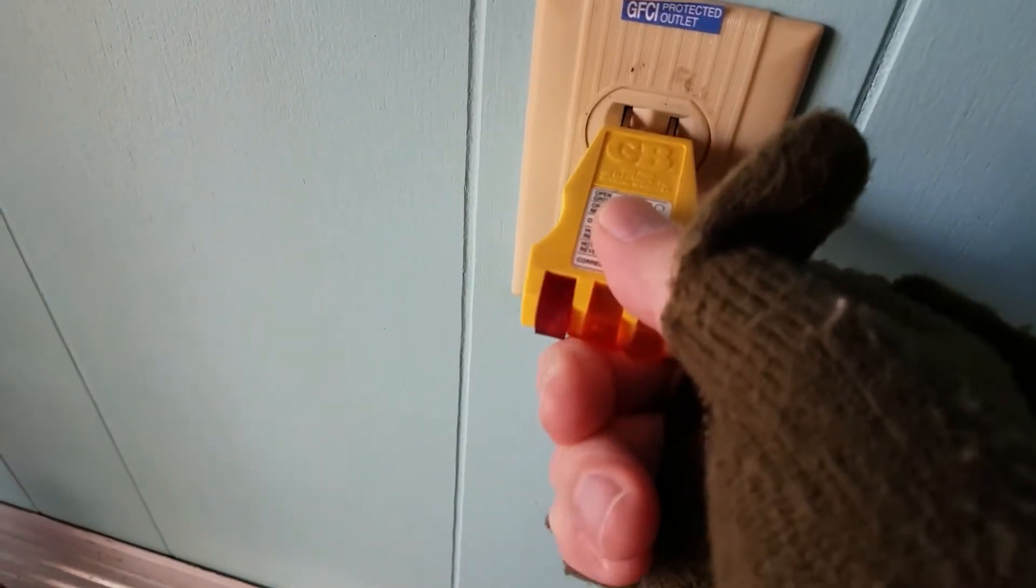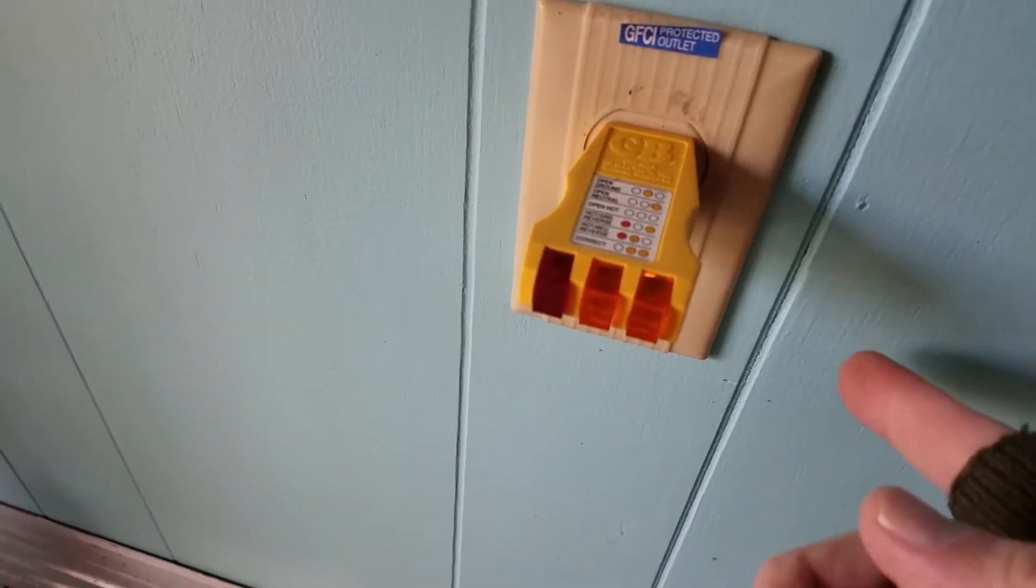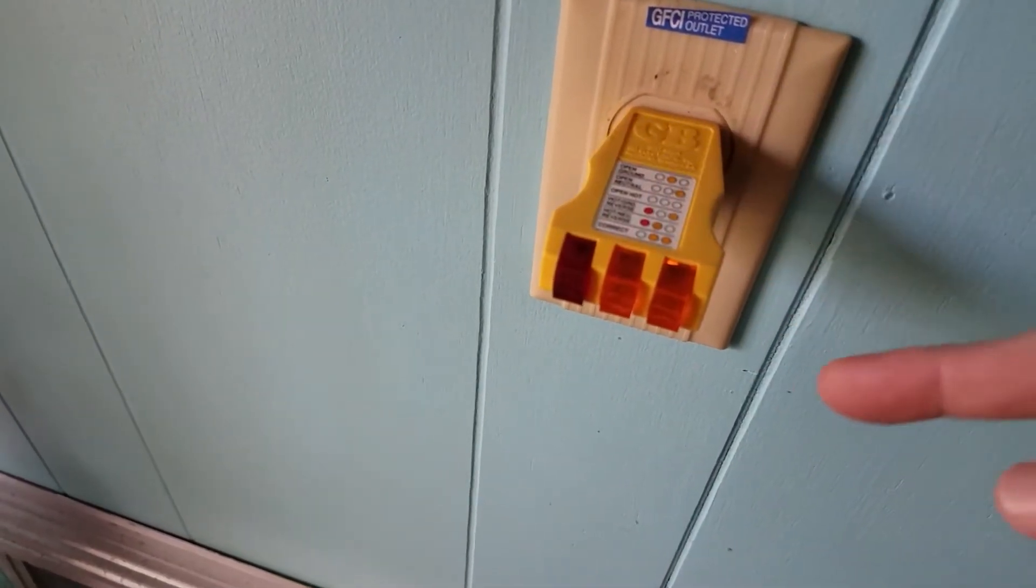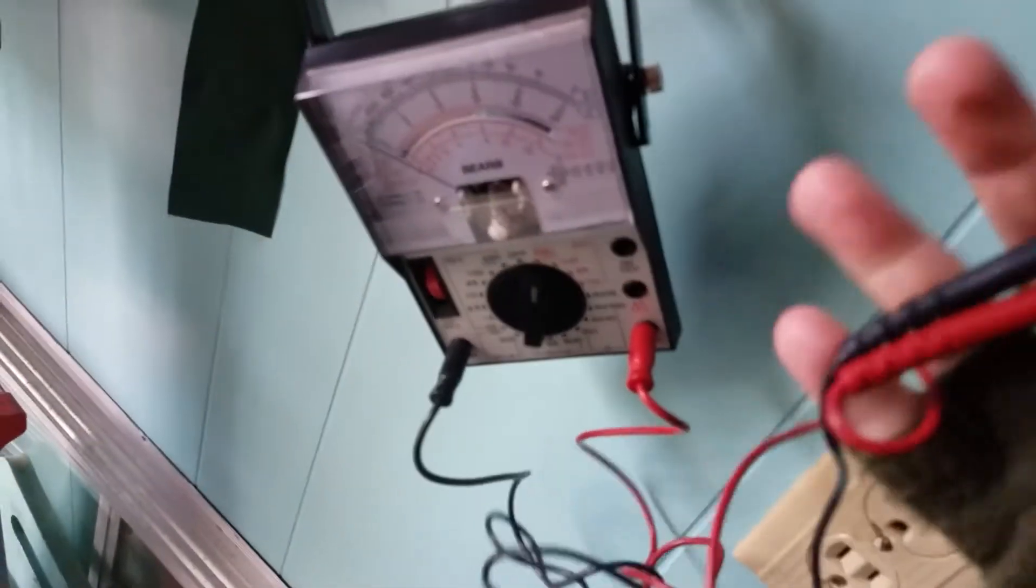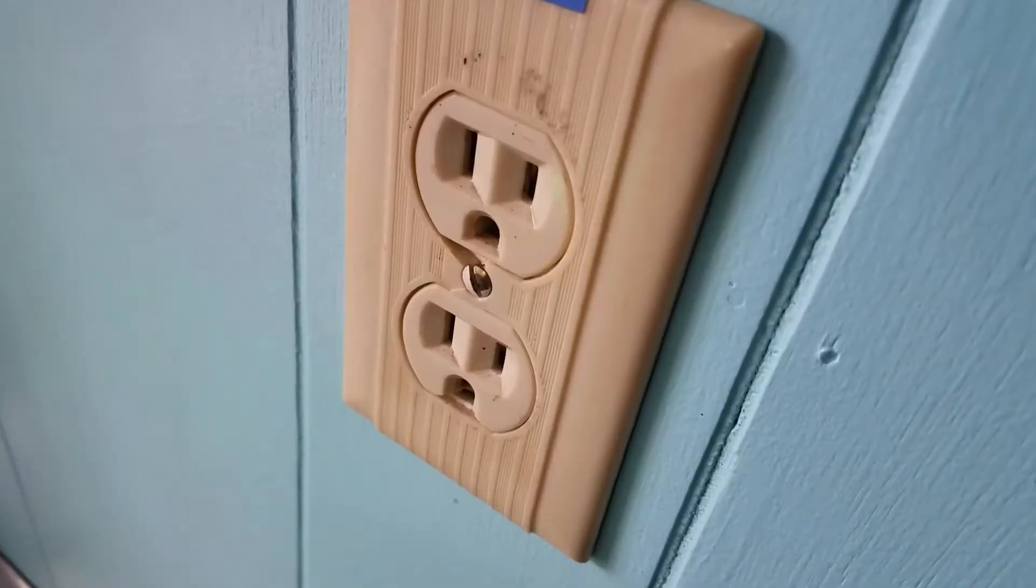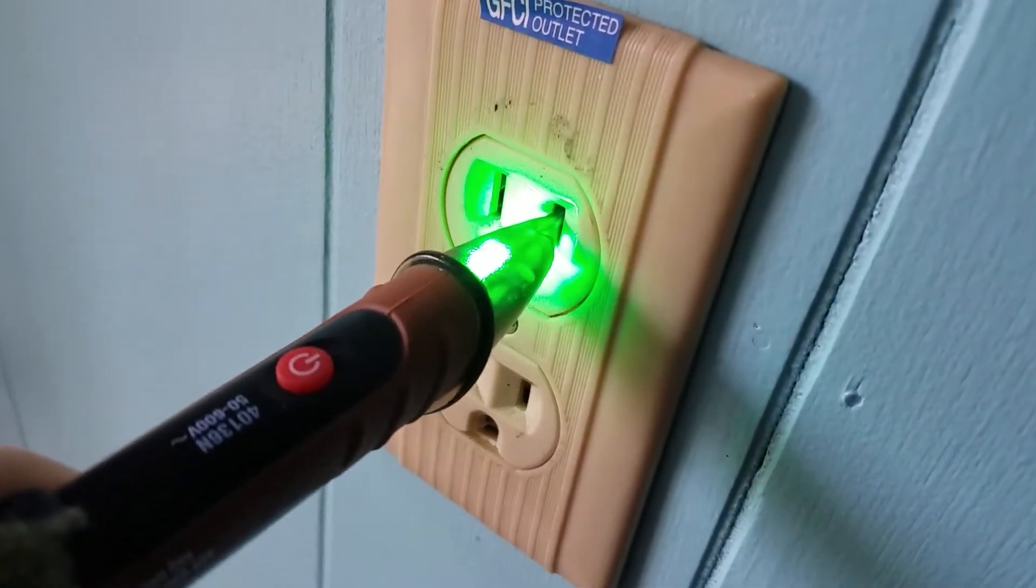We've turned off the circuit breaker. We put in our socket tester and we get no lights indicating one of two things: either no power or an open hot. With the voltmeter plugged in we get zero readings, so we're pretty sure this circuit is dead.